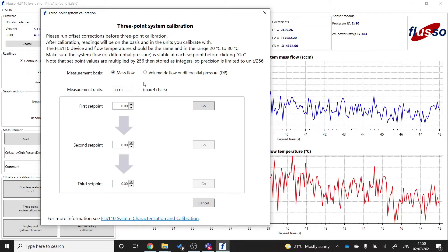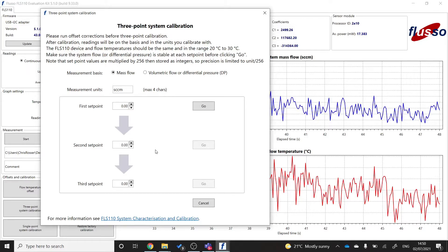Then we'll want to choose the first, second and third set point. And a good rule of thumb, if you're just starting, is to set 10, 50 and 90% of your measurement range.